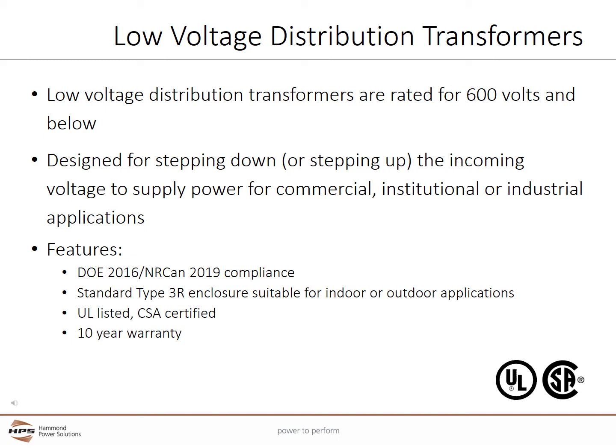HPS Low Voltage Distribution Transformers are designed for stepping down or stepping up the incoming voltage to supply power for commercial, institutional, and industrial applications. Typical features include compliance with U.S. DOE 2016 and Canadian NRCan 2019 Efficiency Regulations. Enclosures are standard Type 3R, suitable for indoor or outdoor applications. All units are UL listed and CSA certified, and all units come with a standard 10-year warranty.